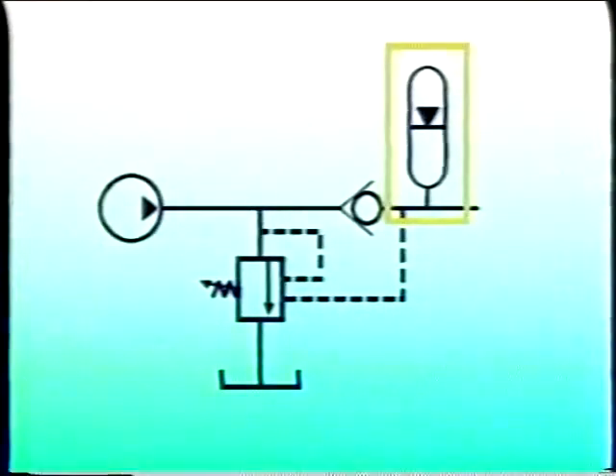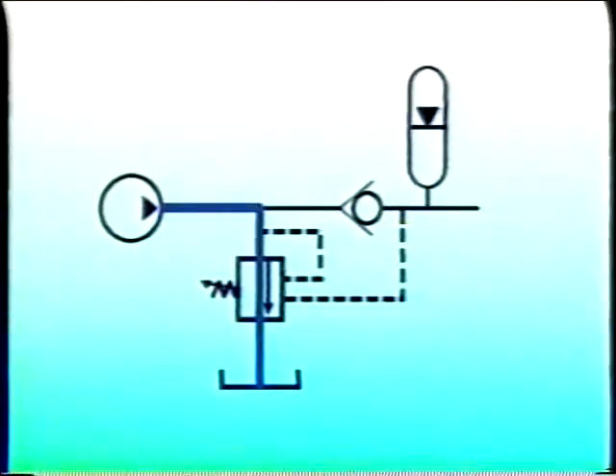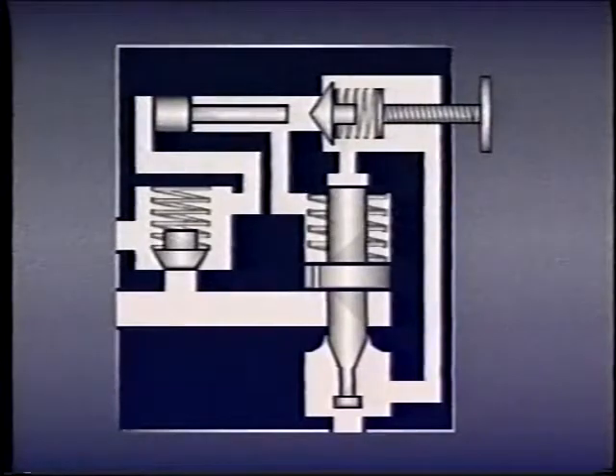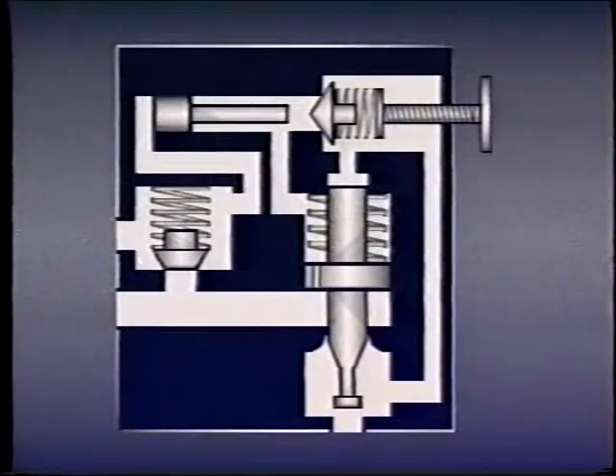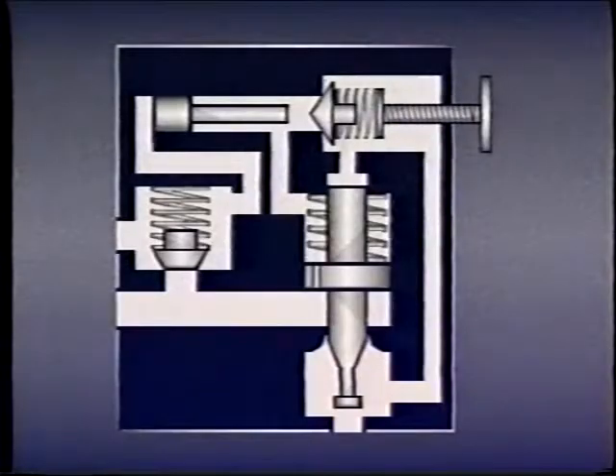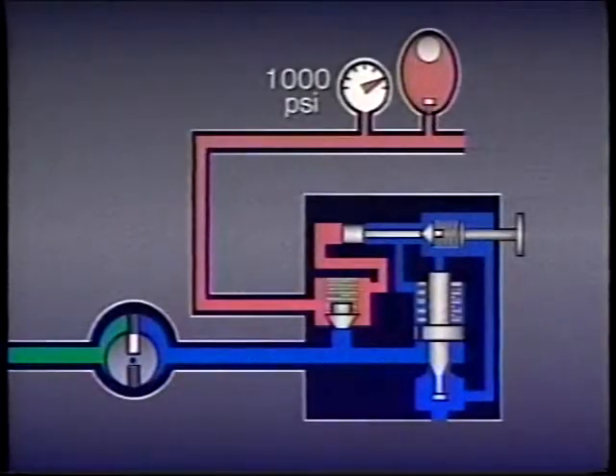Often when an accumulator is fully charged but no work is required of the system for a period of time, the pump is dumped to tank at a low pressure until the accumulator requires recharging. This is called unloading, and it conserves energy and reduces wear on the pump and its motor. One common way of unloading is with a differential unloading relief valve, which is specifically designed for use with accumulators and will automatically divert flow to the accumulator whenever it requires charging, but will unload the pump to tank after the accumulator is charged.